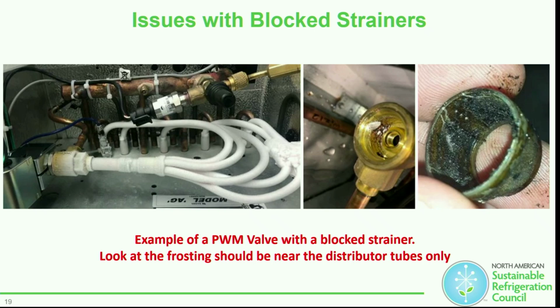Here's an example of what a pulse width valve with a block screen would potentially look like. See how the frosting is happening all the way up to where the cup actually sits inside the body of the valve. Like I stated before, the frosting should happen right there at the distributor tubes, where the nozzle meets. If you see it happen before then, there is something going on. Could be a lack of refrigerant. Could also be that the valve is not opened up all the way.